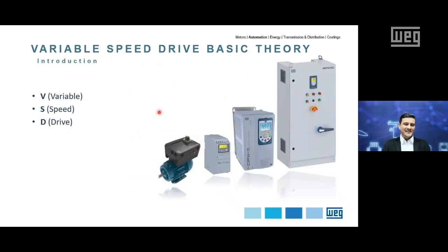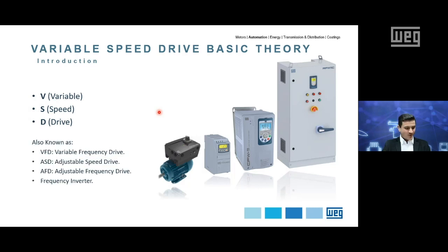So VSD, variable speed drive, also known as VFD, variable frequency drive, ASD, adjustable speed drive, AFD, adjustable frequency drive, or frequency inverter. But at the end of the day, they are the same thing, and it's used basically to control the speed of an AC induction electrical motor. It's important to mention that WEG also has VSDs suitable for PM motors, permanent magnet motors, as well.